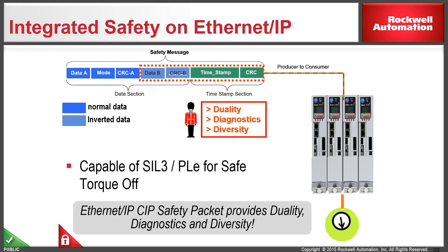So what actually happens when a safety message needs to be sent from a safety PLC down to a safety drive? The way that you achieve higher performance levels for your safety system is through duality, diagnostics, and diversity. If you take a look at what typically happens when a message is sent from a safety PLC over to a drive, basically you'd have two controllers in a SIL 3 application. You'd have the standard GuardLogix controller and then its safety partner. Basically each one of those scan safety code independently. They would then package up a message where you have data A coming from the safety controller and then data B would come from the safety partner. That gets packaged up into one message. So your duality is basically you're sending the same information twice. You're getting diversity in that the information from processor B, the safety partner, is inverted from the data in processor A, so it's diverse. There are checksums associated with this.